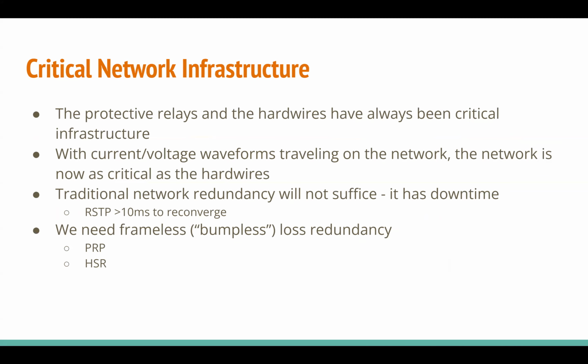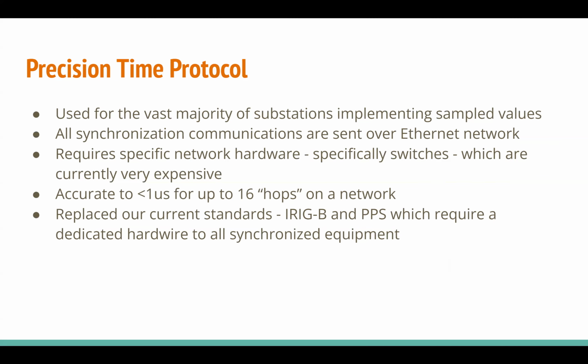How we actually gather or synchronize the time is using GPS signals. You synchronize your clock to GPS so it knows what time it is, and then it distributes that signal on your network with precision time protocol. We use this for digital substations because it meets our 1 microsecond accuracy requirement. Again, this is replacing some of our hardwired connections on a relay, which is another nice benefit.